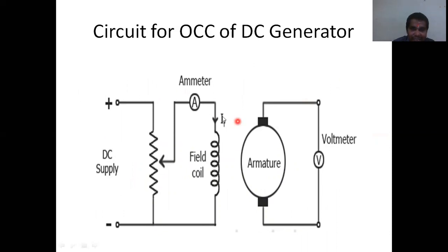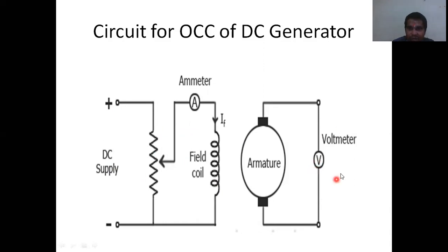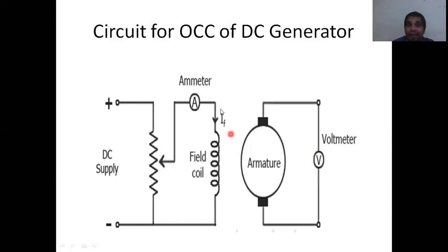Here is the diagram for open circuit characteristics. The field winding of the DC machine is energized from a separate DC source, and the field current is adjusted with the help of field resistance. The voltage across the armature is measured for the corresponding field current, keeping speed constant. You gradually increase the field current and measure the voltage until it reaches its maximum value.